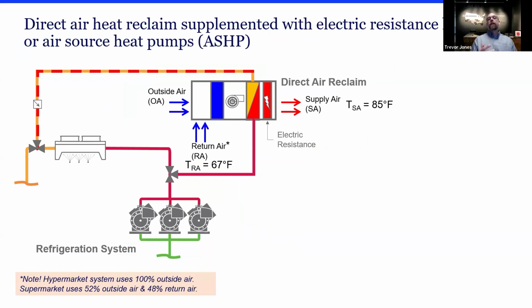So the other system that we looked at for heat reclaim was a direct air system, where we are running compressor gas to a heat reclaim coil in the rooftop unit. There's a diverting valve after the compressors, sending hot gas from the compressors directly to a heating coil, and then it returns from the heating coil as either mixed desuperheated gas or as a liquid downstream of the gas cooler condenser. And again, we're looking at a minimum supply air temperature of 85 degrees.